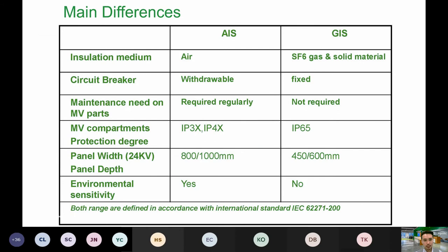Just to share very quickly the key basic differences between the AIS and the GIS. So this one is filled with insulation using air. Here is insulation using SF6 gas. Over in here they have the withdrawable circuit breaker. GIS is fixed. Maintenance is regularly required for AIS, for GIS it is not. The IP compartment rating is IP3X and IP4X. Right, so for GIS it is IP65. The IP rating is much higher.